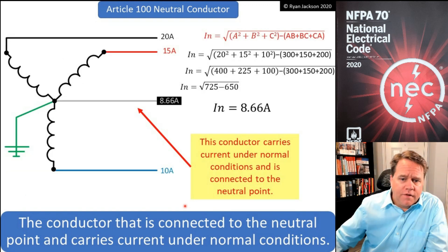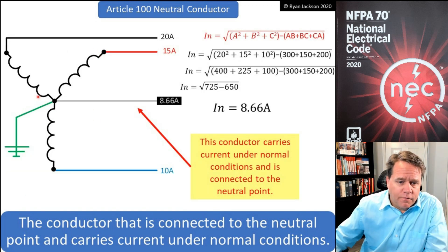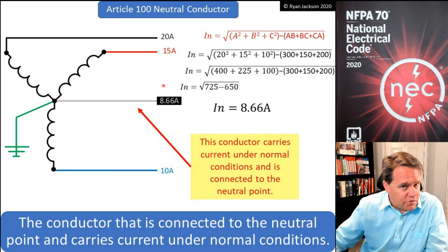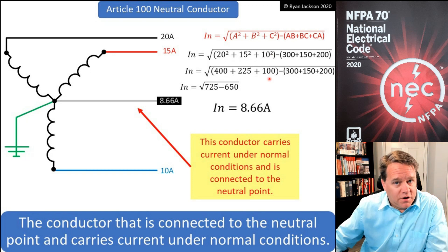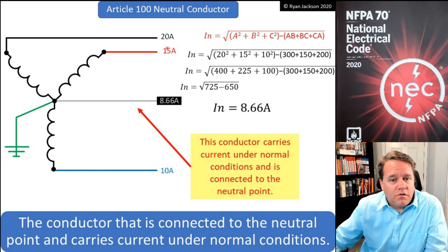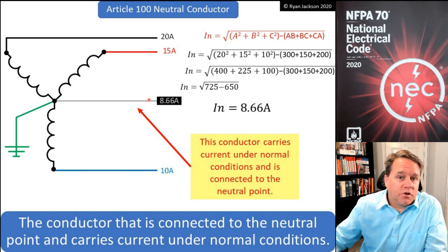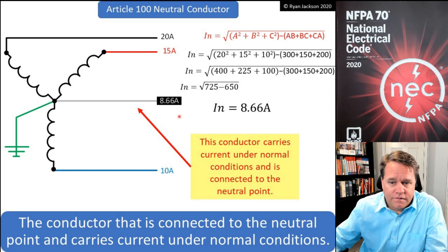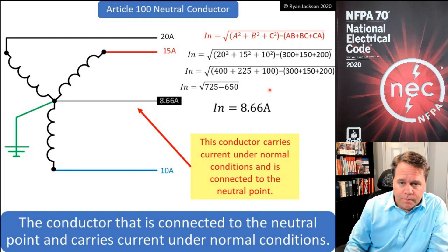On a three-phase four-wire Y connected system, the neutral conductor connects to the neutral point and carries current under normal conditions. For example, with 20 amps on Line 1, 15 amps on Line 2, and 10 amps on Line 3, the neutral current works out to 8.66 amps, which I can calculate using the formula shown here.